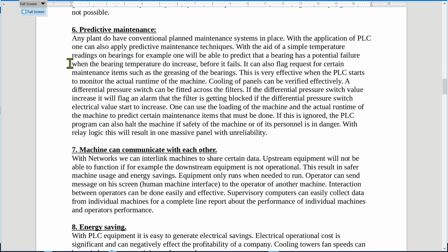It can also flag requests for certain maintenance items such as the greasing of the bearings. All bearings have a certain time interval that is required to do lubrication of that bearing. For example, a certain bearing can have a runtime of 2,000 hours and then it will need lubrication. But this is very effective when a PLC starts to monitor the actual runtime of the machine. We can even do a software program where it will monitor the loading of the machine and the runtime of the machine. And based on these two parameters, we can then predict at what time it will be needed to lubricate that machine again. And there are various examples of this.